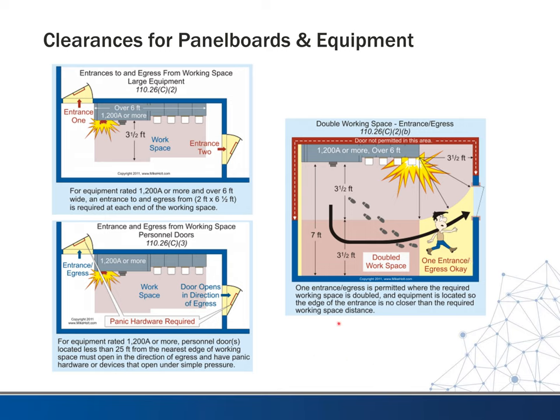So as you're designing buildings and you're going to have a main electrical room, you need to be aware of what size switchgear you're going to have in there. And with that, you'll want to give allowance for the space needed, either an egress path, either two doors or one door with double the clearance. So, just keep that in mind as we move forward.